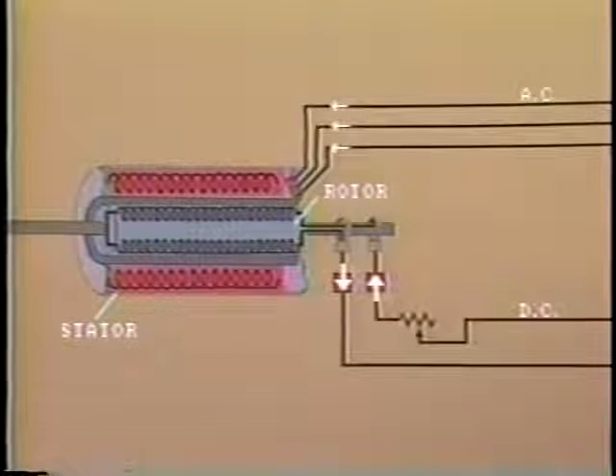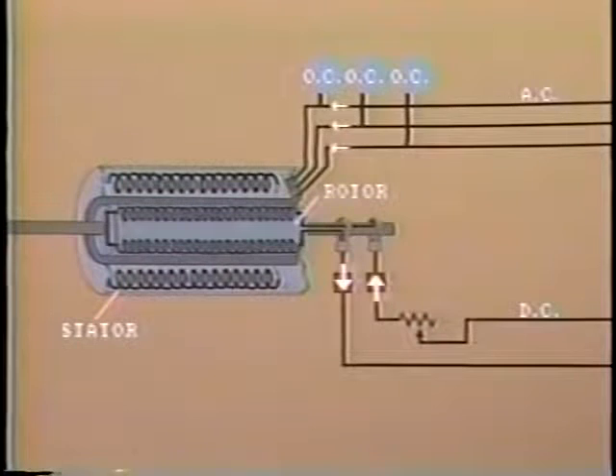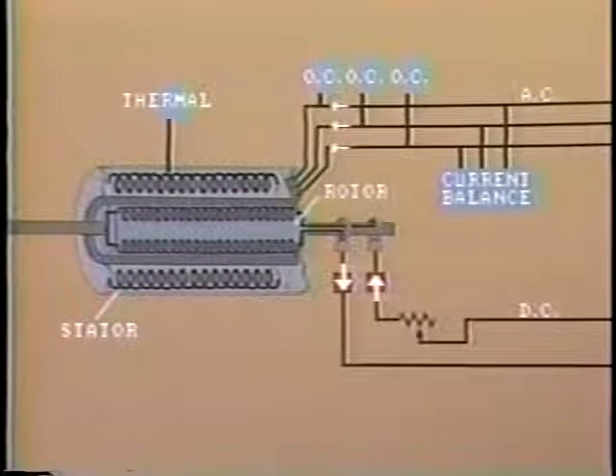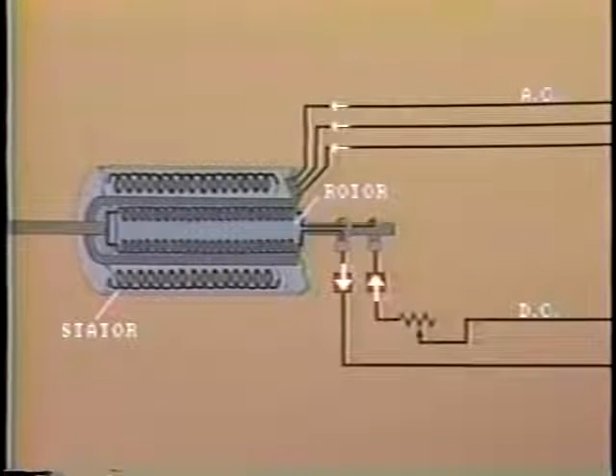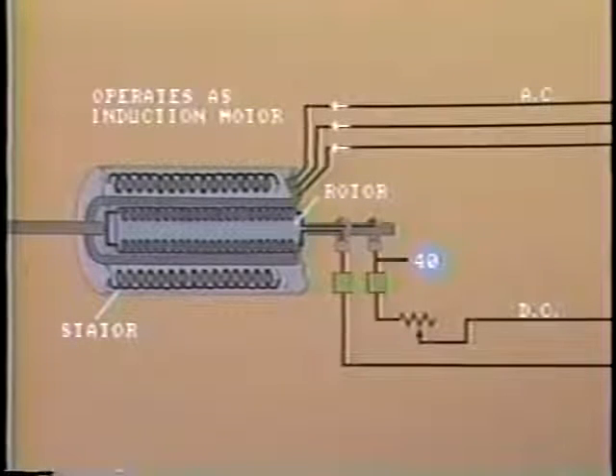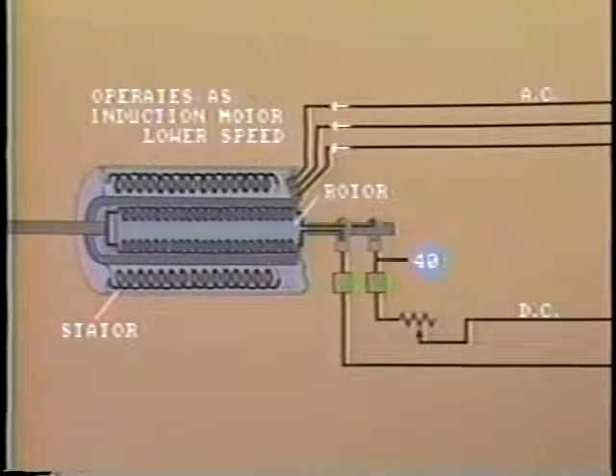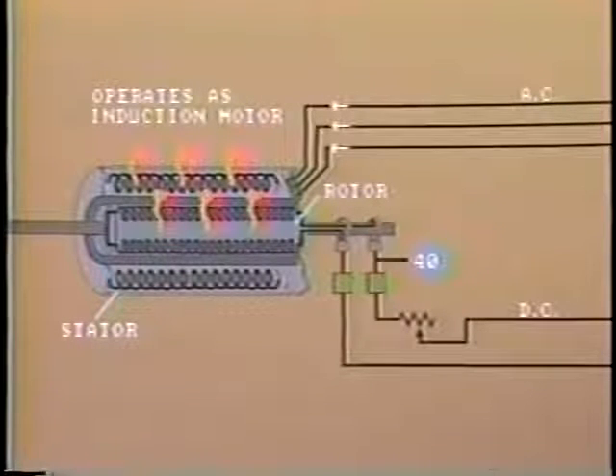Overheating of the stator winding is protected by overcurrent relays, thermal relays, and current balance relays, just the same as the large induction motor. Another relay often found on synchronous motors is the loss of excitation relay, 40. If field current is interrupted for some reason or another, the motor will operate as an induction motor at lower speed, drawing a heavy reactive load from the power system. This will cause serious overheating of both the rotor and the stator windings.